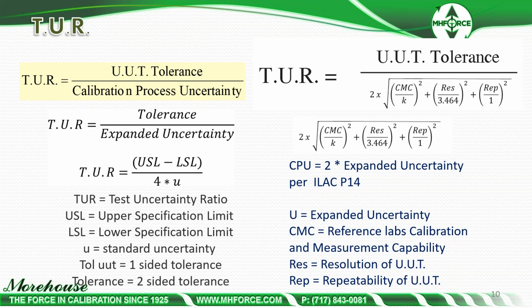I don't like 4 times U because you don't know what you're working with as far as probability and confidence interval. So it's usually K, and it's usually 2 times the expanded uncertainty. If you want 95% confident, it can be 1.96. It just depends on how things work out in the equation. But this denominator here, the calibration process uncertainty, comes specifically from 2 documents.